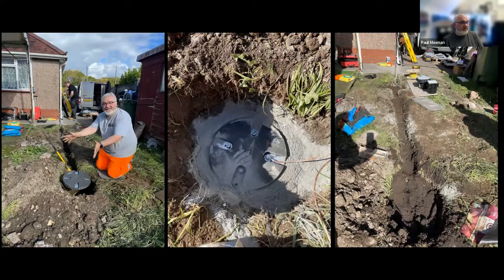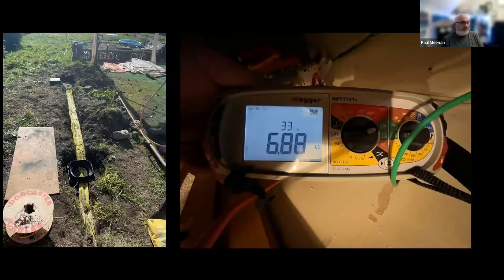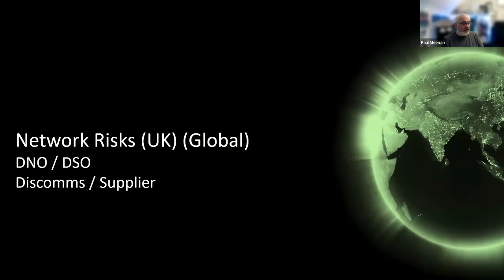What we were doing was replacing a very good friend of mine's earth electrode, which had rotted and corroded. So we put two discs in, dug a small trench, laid bare cable, and got some fresh soil, covered it up. We got 6.8 ohms, which is very good considering the recommended 21, 200 ohms. So that's pretty stable, pretty good. That was a job I did recently, in the last year or so.